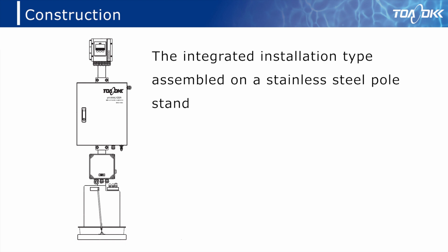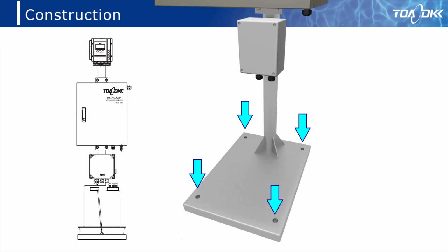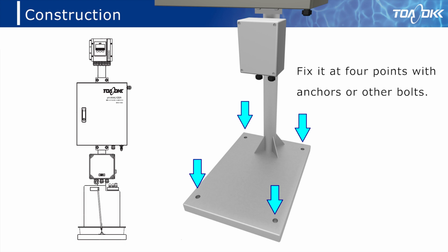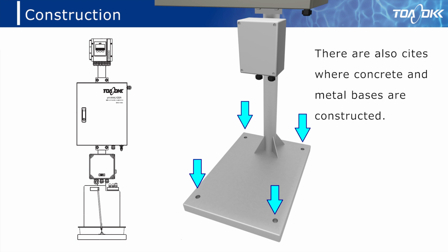The integrated type is the standard specification of the main unit. Assemble the transmitter and the liquid feed control unit to the stainless steel pole stand. Fix the base with the pole stand for installation. Fix it at 4 points with anchors or other bolts. There are also fields where concrete and metal bases are constructed for anchors.